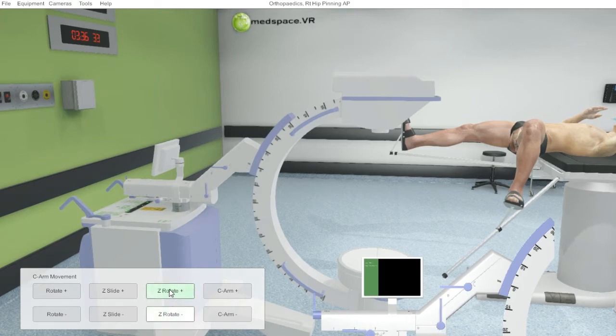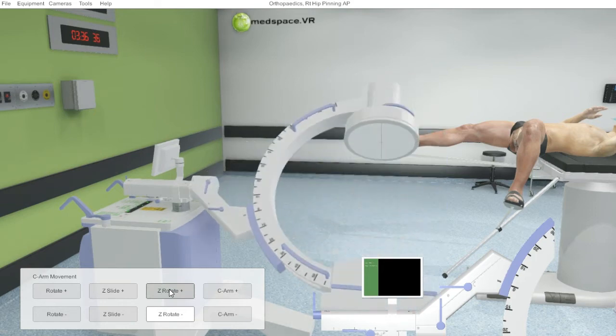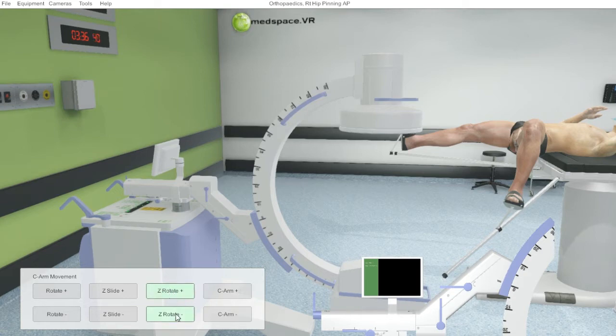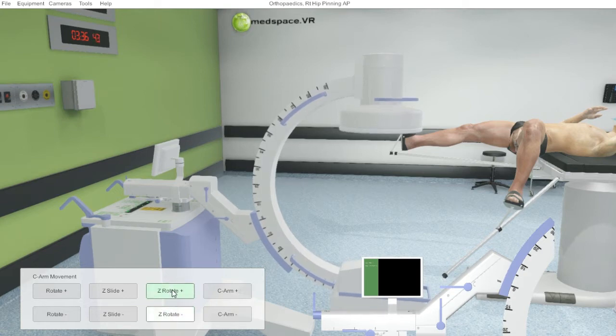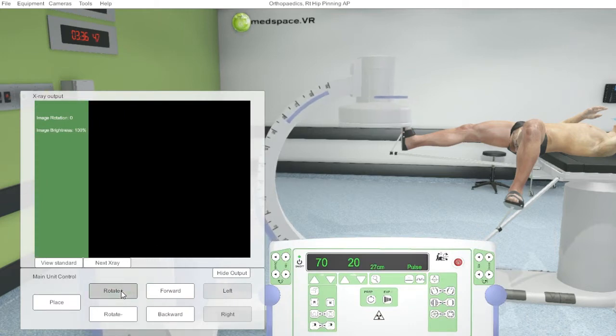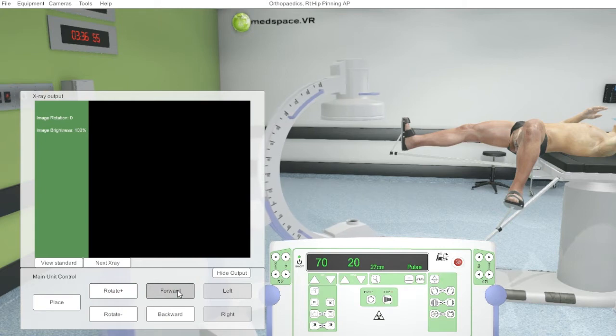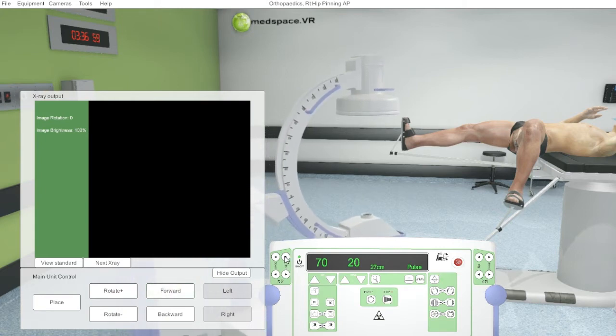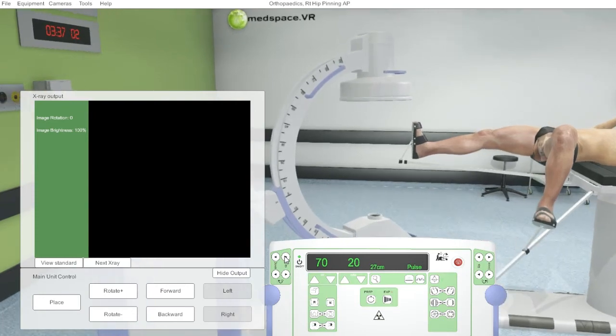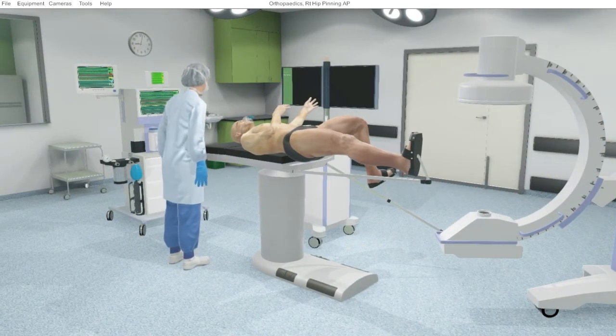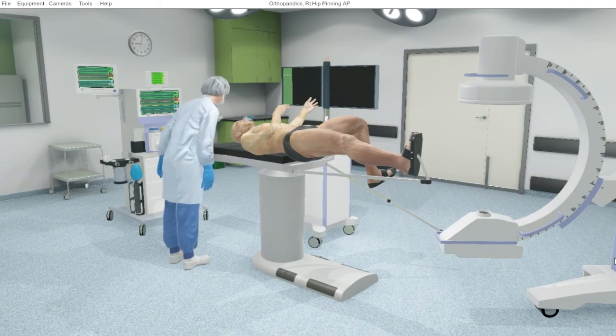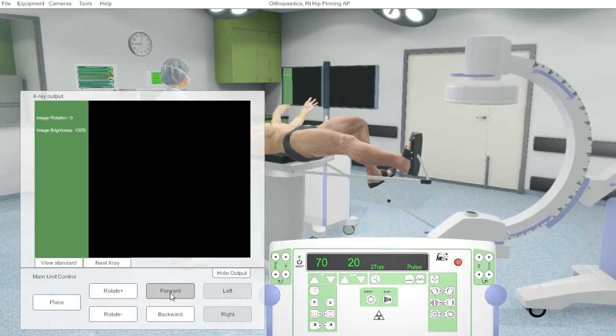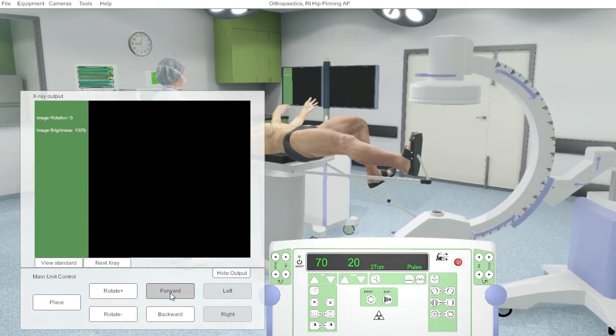The C-arm can be manipulated by using the locks on the actual arm itself, or on the base there's height adjustments and the base movements. You can move the entire base forward. As you can see, the actual handles on the base are in the direction of the movement. Otherwise, you can click those handles sideways and then you will enable left and right movement.